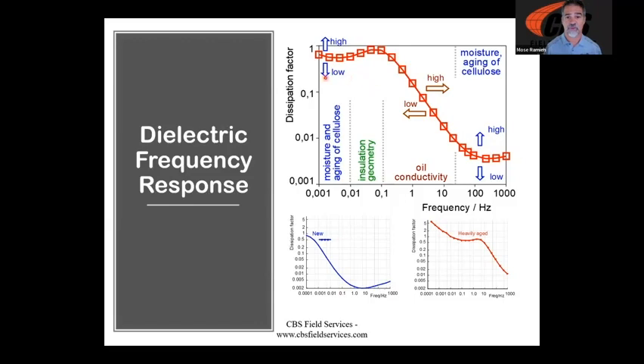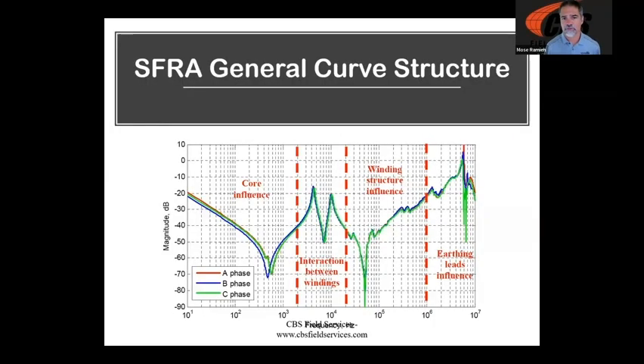And that test basically does a power factor from 0 Hertz all the way up to 1,000 Hertz. And once again, looking at how that transformer responds. And once again, a new transformer is going to be the curve similar to this. An aging transformer is going to push up and to the right. And once again, this is some of that new technology.